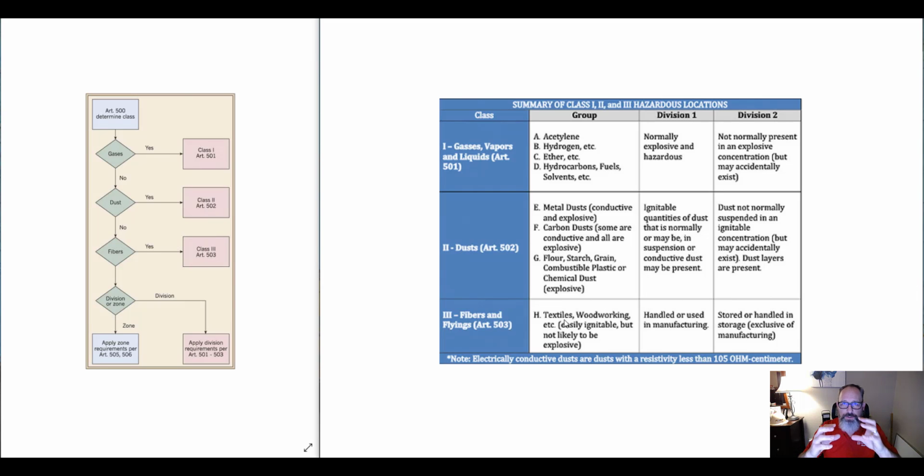And when I pulled it out, you could see the burned, charred dust in the back where it finally had arced on the contacts and caused it to trip the breaker. So some of these areas that you just may not think about could become an ignitable situation down the road.